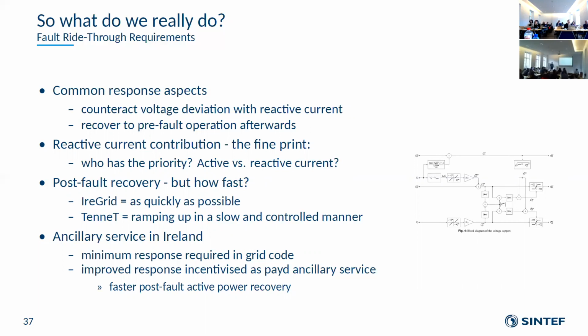If we have full active current, maybe even the voltage was a bit low, so we were at 110% of the current already to compensate for the lower voltage, and then we have to supply reactive current support at the same time. While we're already at full active power, our converter doesn't give more, so we run into limitation. What do we do then? We have to do active and reactive power at the same time. In some regions, we have to prioritize one, and in other regions, we have to prioritize the other. This really affects the wind power plant itself, because once you have to prioritize reactive power, you cannot have the active power anymore. That means you cannot get rid of the power you actually harvest from the wind, at least not for some time, so you have to get rid of that energy in some way.